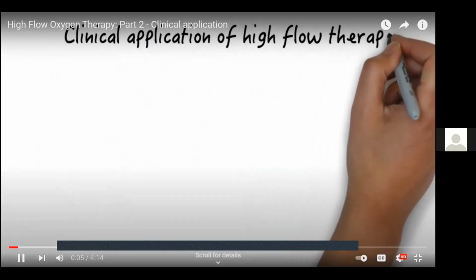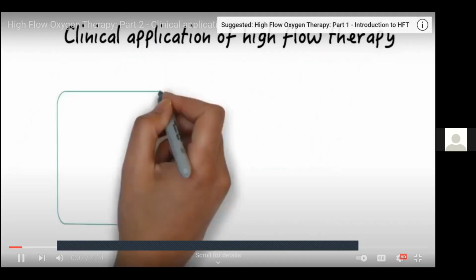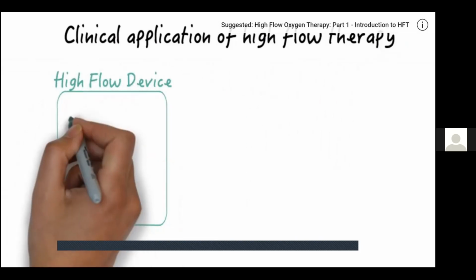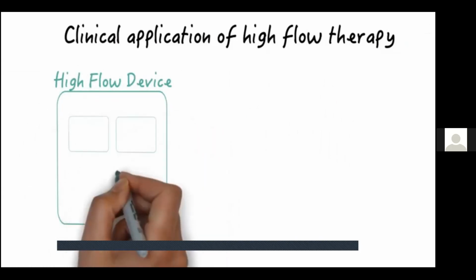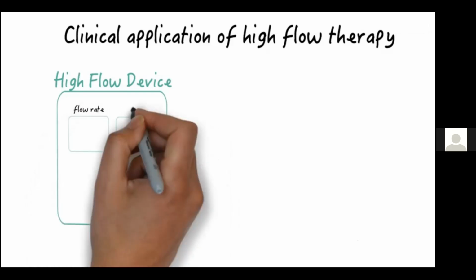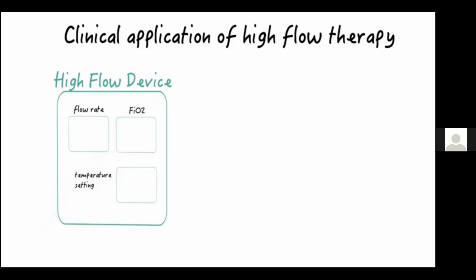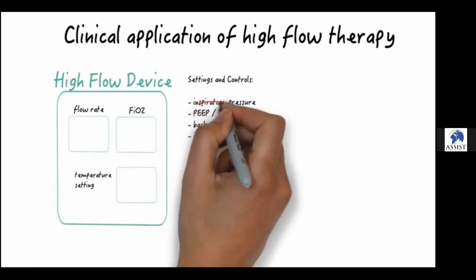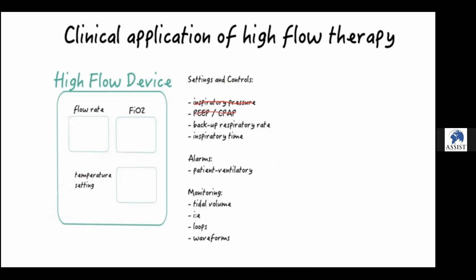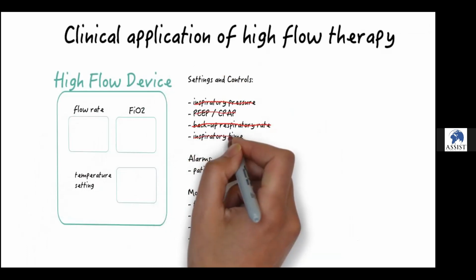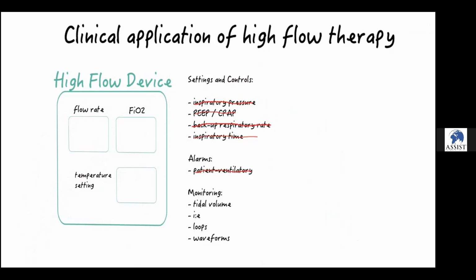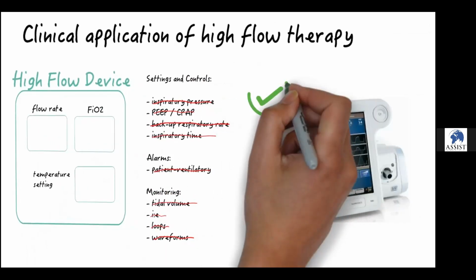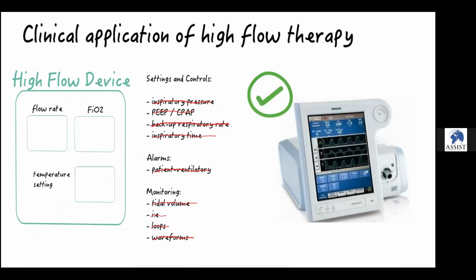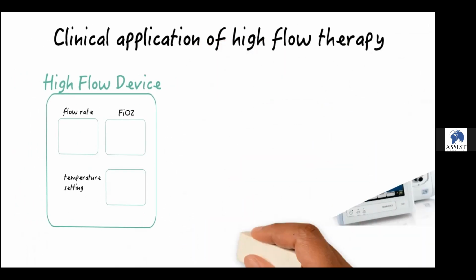In this video, we'll quickly highlight the clinical application of high flow oxygen therapy. We already discussed that high flow therapy is not a replacement for non-invasive ventilation because it is not capable of providing the same level of ventilatory support like NIV. In high flow therapy, for example, there is no inspiratory pressure setting, no PEEP or CPAP setting, no backup respiratory rate setting, no inspiratory time setting, no patient ventilatory alarms. You also cannot monitor the tidal volume, the I:E ratio, and there are no loops or waveforms. You get the idea. NIV, on the other hand, can provide all of these. In fact, the only two main controls on high flow therapy are FiO2 and flow.